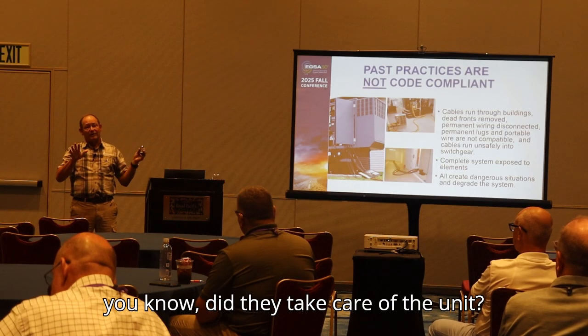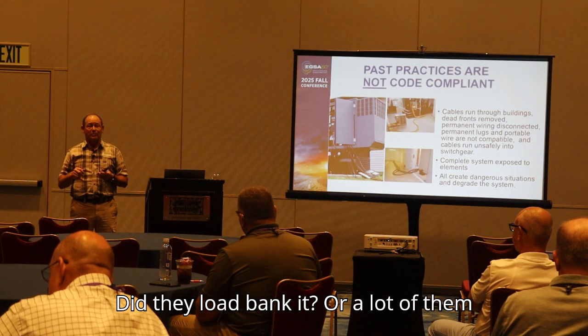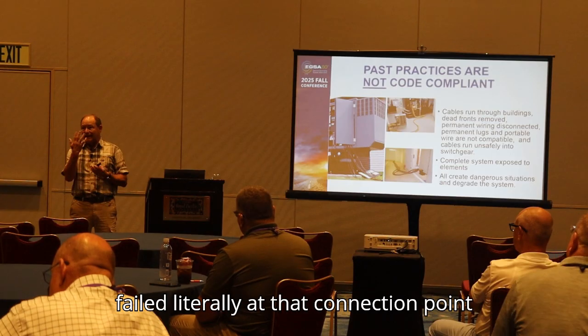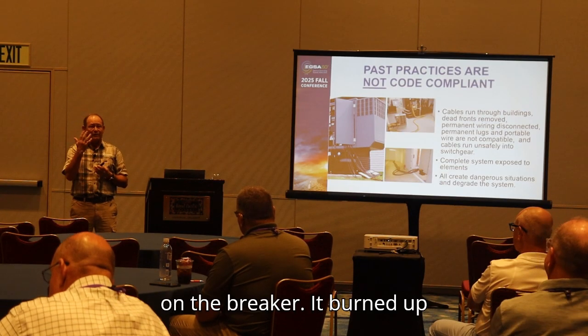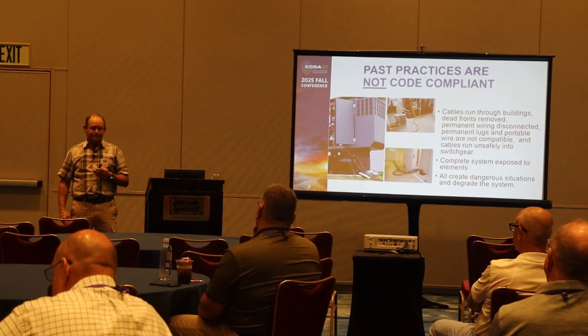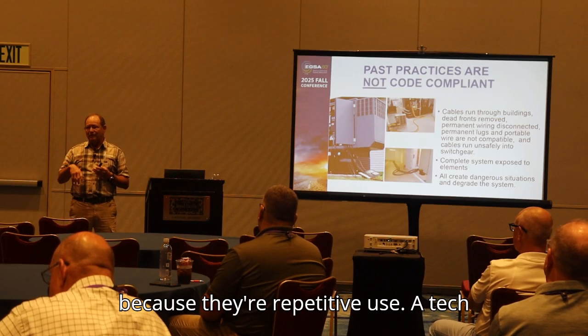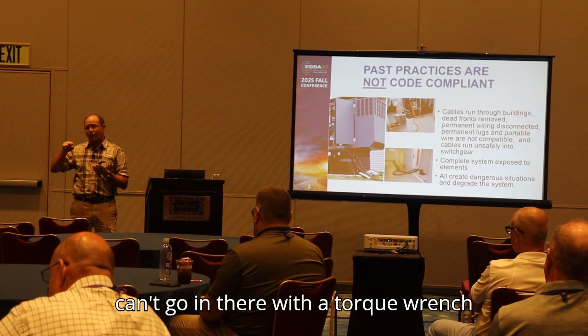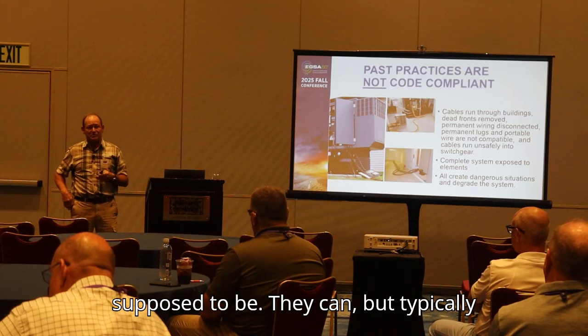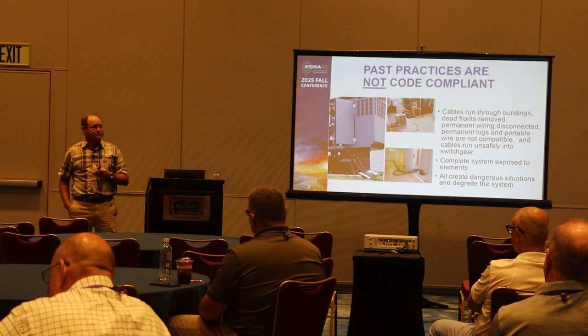It depended on whether they took care of the unit, whether they load banked it. A lot of them failed literally at that connection point on the breaker, burned up because they're repetitive use. A tech can't go in there with a torque wrench and set it back exactly the way it's supposed to be. They can, but typically they don't.